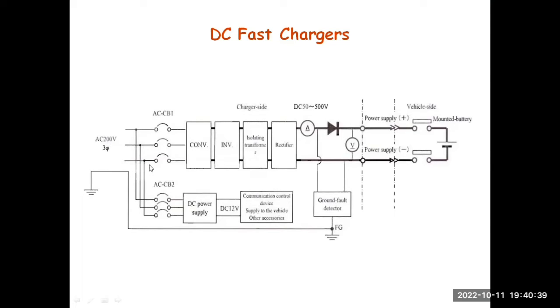You have a circuit breaker, generally an MCB or a molded case circuit breaker, MCCB. Either MCB or MCCB is used for this application. MCB has got a magnetic tripping as well as thermal tripping. Similarly, MCCB also has magnetic as well as thermal tripping. Whereas for higher current applications, MCCB is used. For lower current applications, up to maybe 63 amps, MCBs are used. MCBs are cheaper compared to MCCBs.